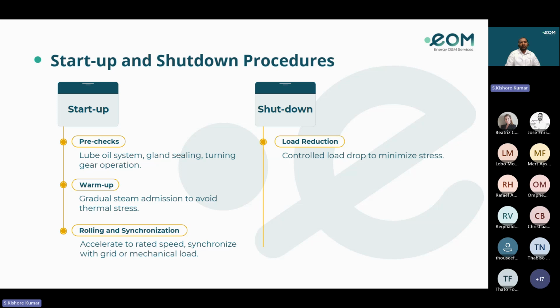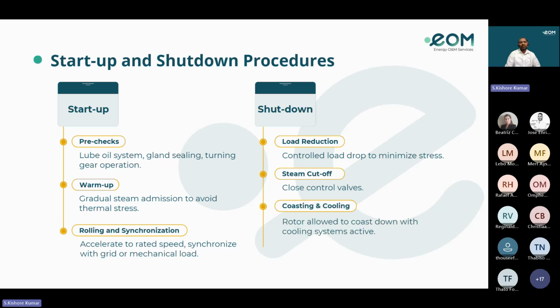Coming to the shutdown: load reduction, controlled load drop to minimize the stress; steam cutoff, closing the control valves; and coasting and cooling down, which allows the rotor to coast down with the cooling systems active. Turning gear: post shutdown, the turning gear is engaged in order to avoid shaft bowing.